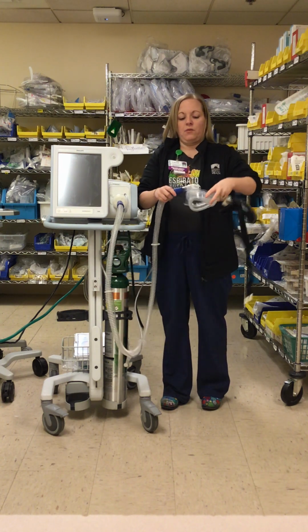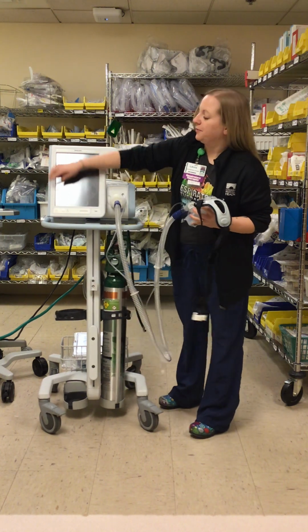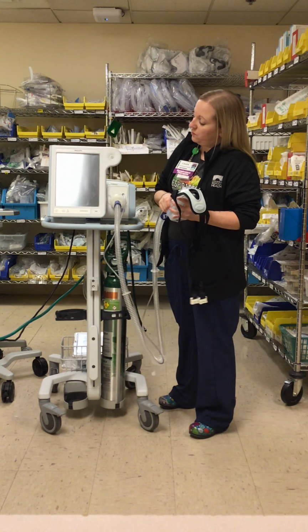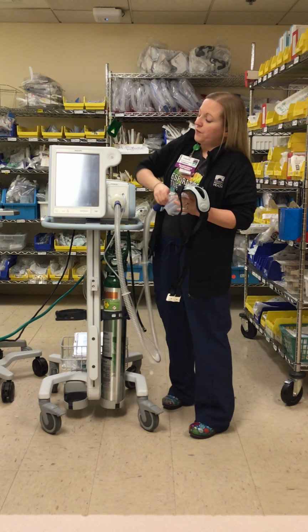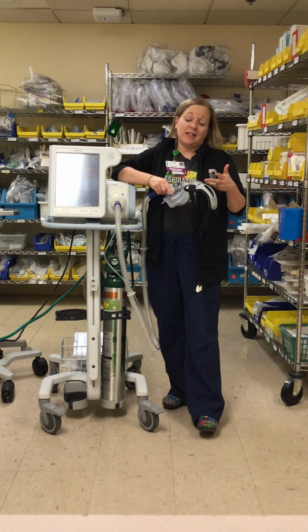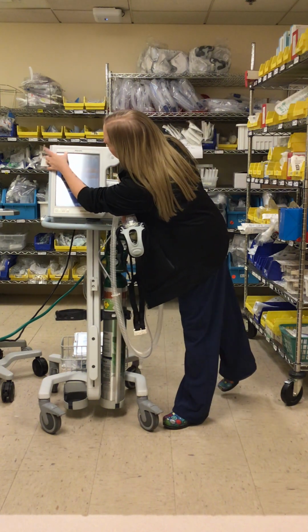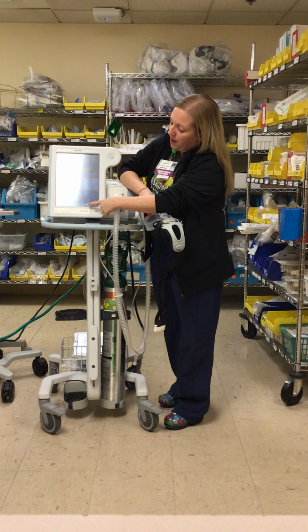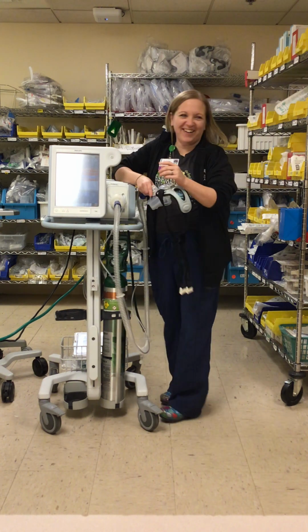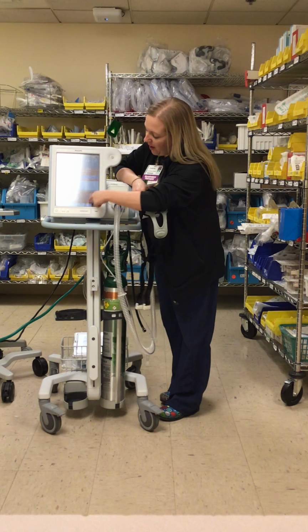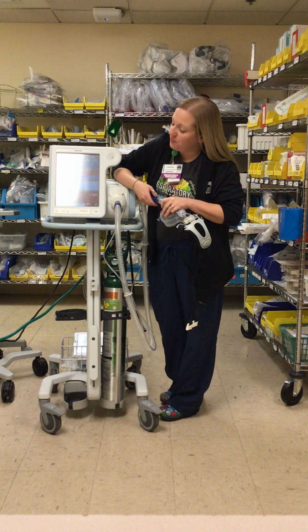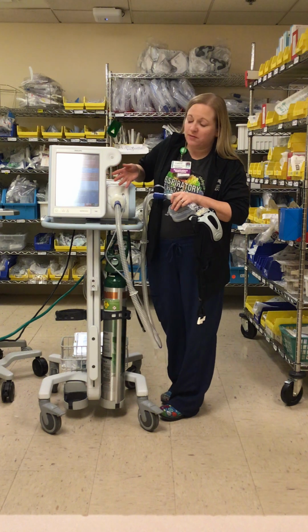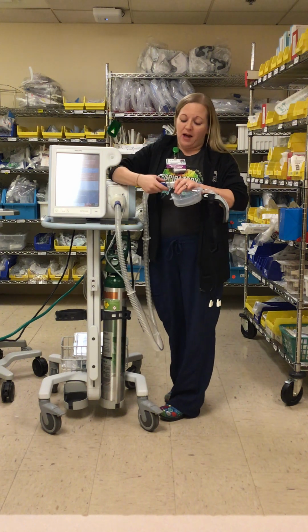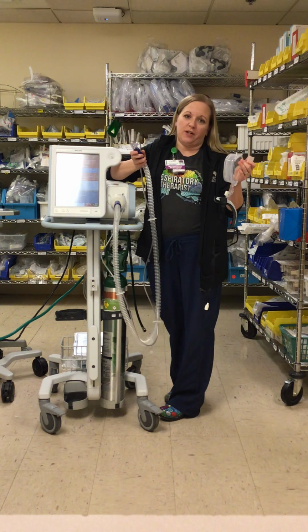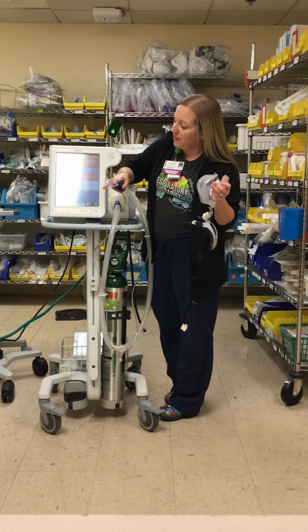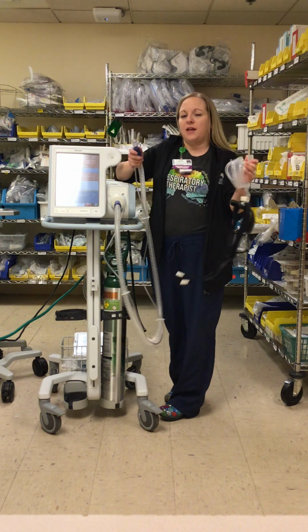The second thing we will talk about is the unit itself. So the first thing that a lot of people ask about is how to put the unit into standby. So on the touch screen on the bottom right hand side is the standby button. If you tap that, give it a few seconds, the machine should kick into standby like it just did. Sometimes it will not kick into standby unless you actually disconnect the mask from the circuit. So if you have a machine and you hit standby and it continues to cycle, just take the mask off.